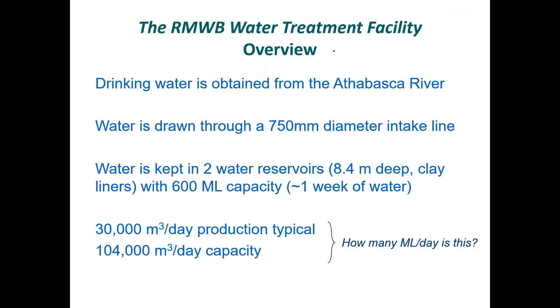Having reservoirs is good because sometimes we want to stop our intake from the river. During ice breakup, they stop taking water — the turbidity goes from the dozens to the thousands within a matter of hours, and it's not worth cleaning that water. They let all that flow through and take the water back when it's cleaner. The plant runs at about 30,000 cubic meters per day — that's 30 million liters. The capacity is much larger to allow for population growth or events like forest fires.